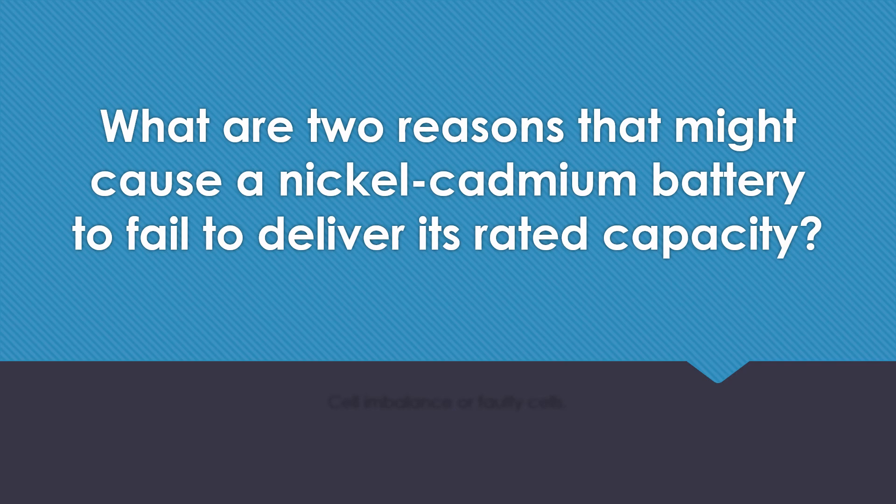What are two reasons that might cause a nickel-cadmium battery to fail to deliver its rated capacity? A cell imbalance or faulty cells.